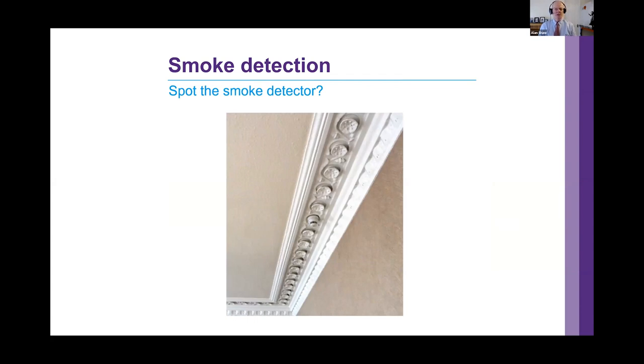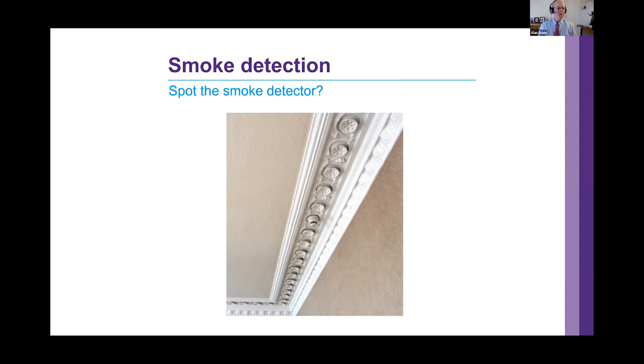Fire safety notices are a mandatory requirement. An automated means of fighting the fire, if appropriate, may include sprinkler systems. Provision of manual firefighting equipment — with fire extinguishers, hose reels, fire blankets, etc. Safe means of escape leading to an unhindered place of safety. And provision of at least one, and preferably two or more, fire escape routes which are protected and lead to safety within a specified maximum distance, where people are sleeping, studying, living or at work. This protected route should lead to a place outside the building, or alternatively — in an evacuation within a building, such as at an airport or a shopping mall — going outside isn't always the safest option, particularly in London or other major cities with traffic and narrow pavements. Provision of adequate escape lighting, with prescribed wayfinding, direction pointers and signage, and fire safety notices.